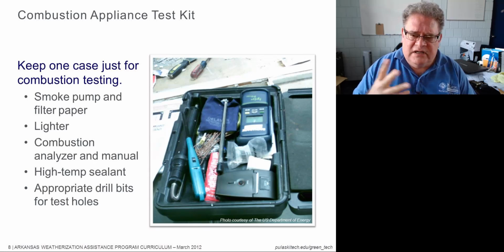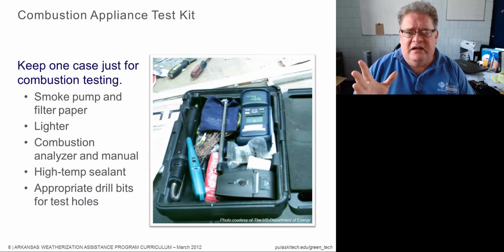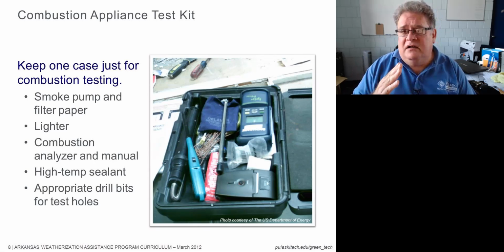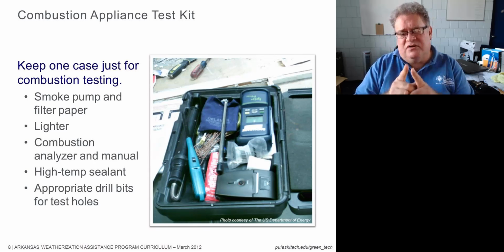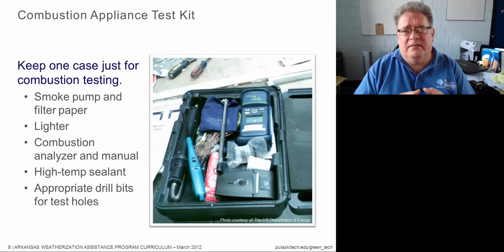So you can take a $100 or $150 sensor and clog it up. It may have almost zero life left after that. That's why you take a sample with the smoke pump first. If it's at a certain level or below, then it's safe to put your combustion analyzer in it. It won't soot it up too bad.